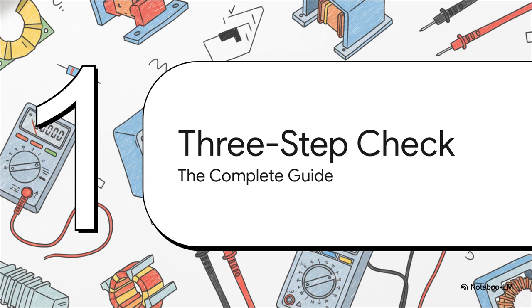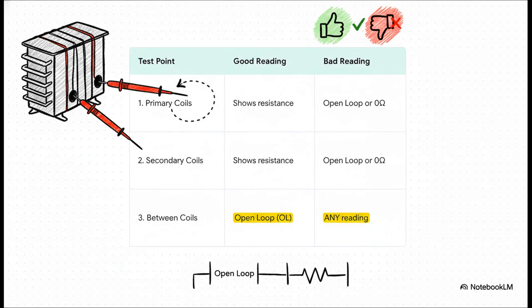So let's put all of this together. We're going to create a simple, foolproof, three-step check you can use every time. This little table right here is basically your complete diagnostic cheat sheet. Step 1, check the primary coil. You want to see some resistance. If you get an open loop or 0 ohms, it's bad. Step 2, check the secondary coil. Same deal, you need a resistance reading. And then, step 3, the big one, check for isolation between the primary and secondary. Here, the only good reading is open loop. Any other reading, any beep, any number at all means failure.